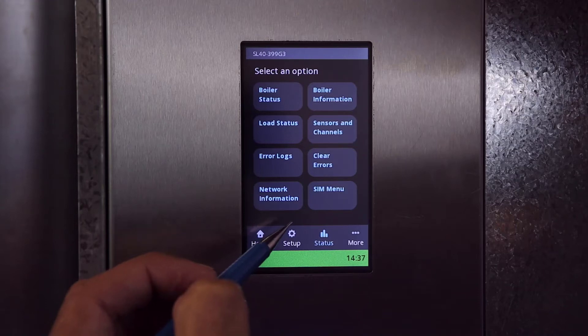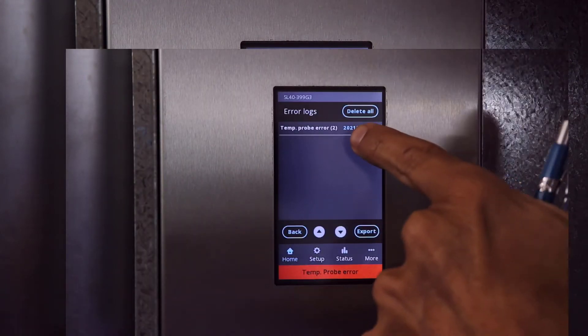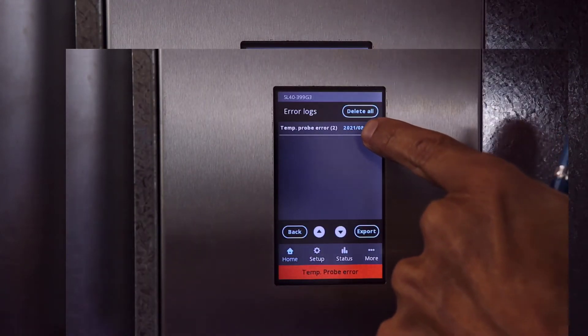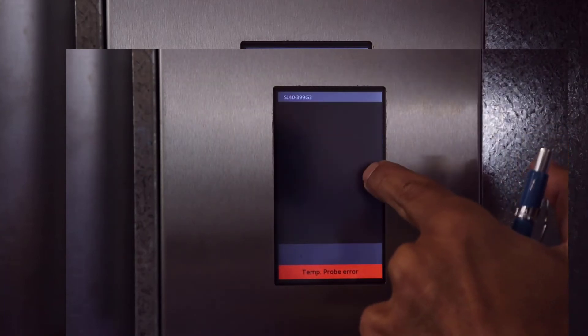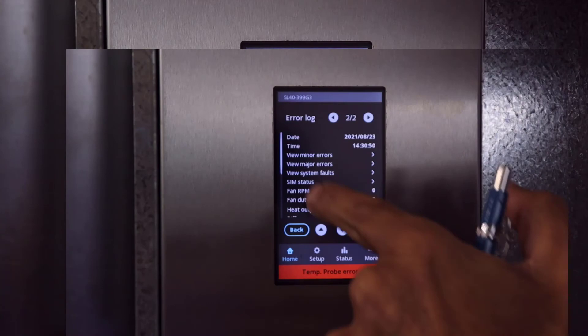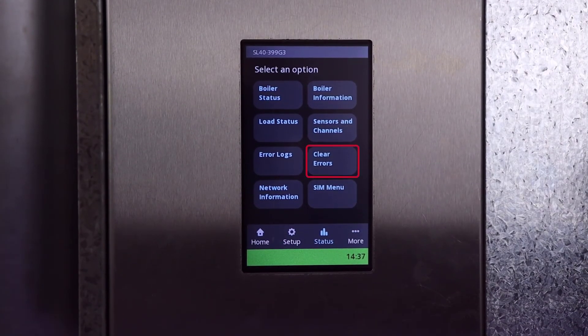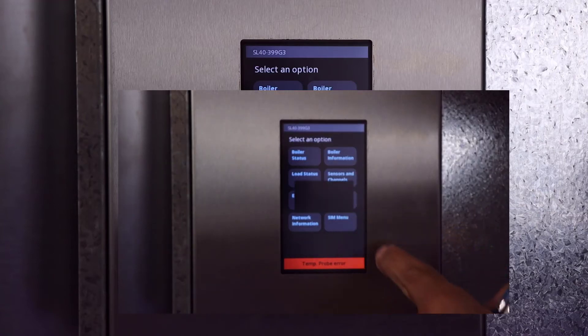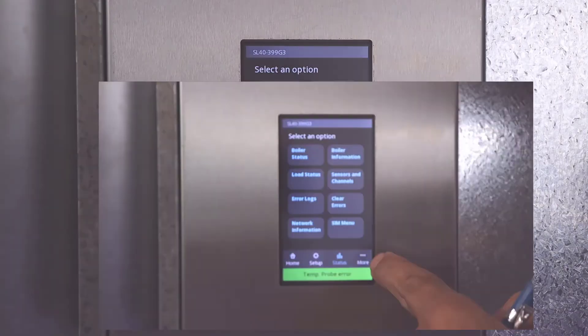The error log has been improved, now in a historical list format. The number of times a particular error has occurred is in brackets, and by selecting the type you have access to all the recorded details. You do not need to delete errors to reset the boiler. You can also see Clear Error here, which was previously under Advanced Diagnostics. This is where you can clear an error status to allow the boiler to attempt to fire. When successful, you will see the red bar at the bottom of the screen change to green.